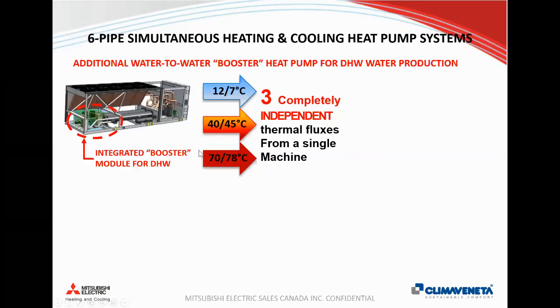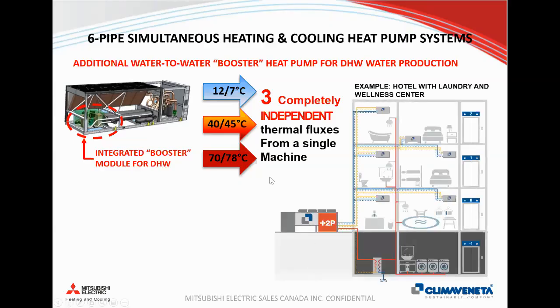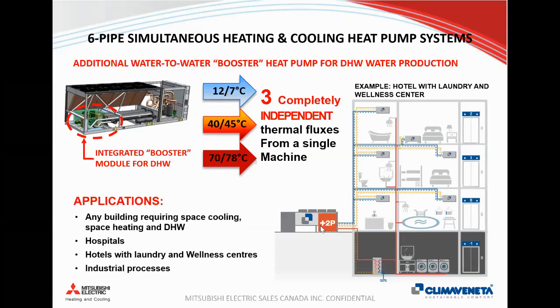There's also 6-pipe system, so those are similar to 4-pipe, but they also have an integrated booster module on the heat pumps for it that you can use 6 pipes throughout the building. So 2 for cooling, 2 for heating, and then another 2 specifically for very high temperature for domestic hot water. So basically any building where you have heat to be recovered or require heating, cooling, and domestic hot water year round are places where you want to use that.